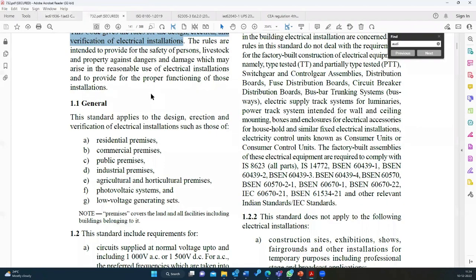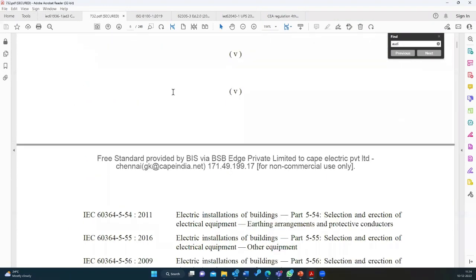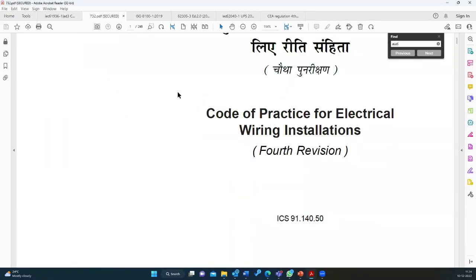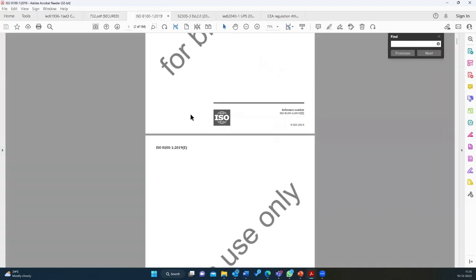I'm also showing you the standard IS 732, which all of you know very well. Nowadays, we talk more about IS 732, the Code of Practice for Electrical Wiring. This is the Indian standard. Here also, I am checking the word audit. There is no word called audit in this particular standard, whereas verification appears in almost 77 places. Similarly, I'm showing you the ISO standard for lifts. Audit is never there, only the word audible. Whereas verified is used in 24 places, and verification in 18 places.